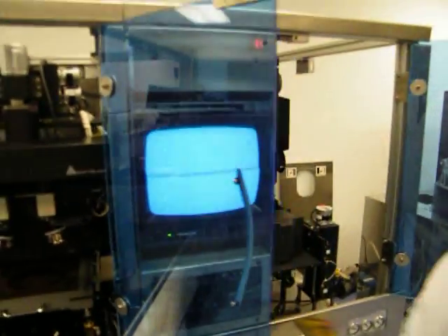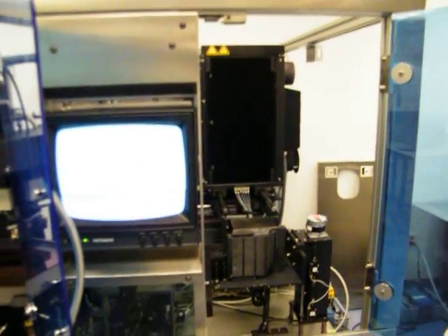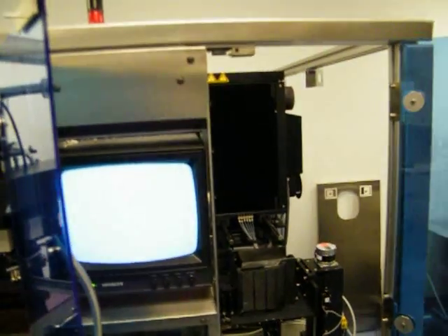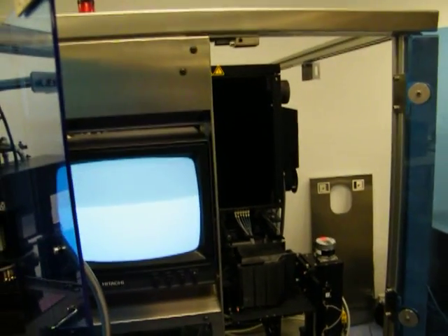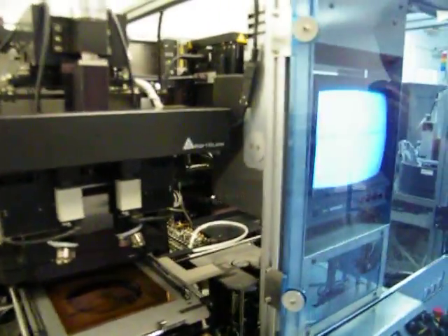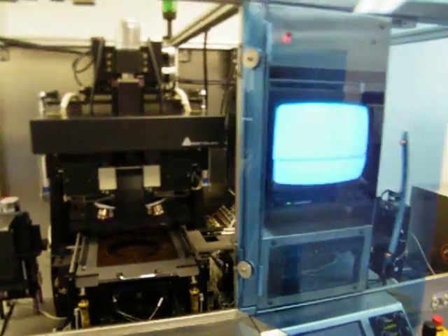Optics were checked, cleaned, and reinstalled. We have a brand new lamp, a new ellipsoidal mirror, integrator block, condenser lens, fly's eye lens, all cleaned, inspected, reinstalled, and set up.